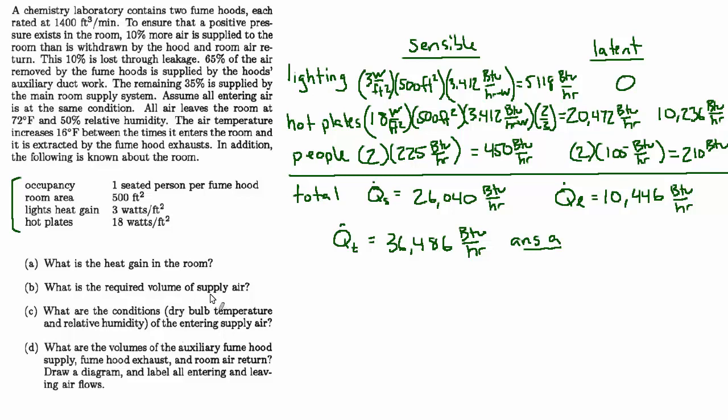If you want to check that, you can calculate the sensible heat ratio. It looks like it's going to be about 26 out of 36, which is just a bit over 70%. So it's a bit low, but it's in the ballpark. I think this assumption is reasonable.